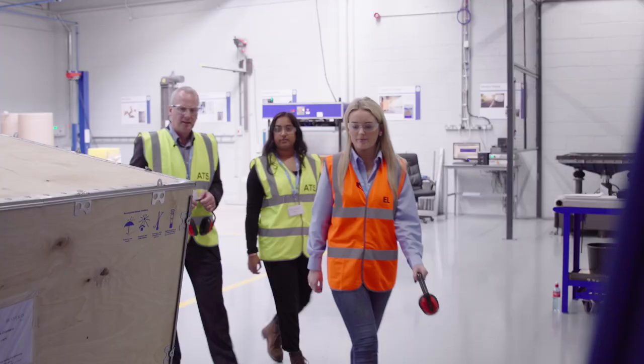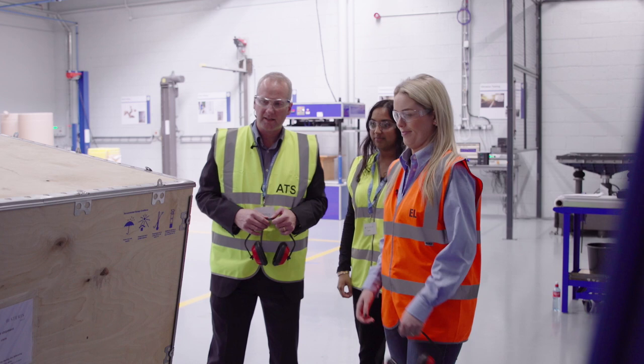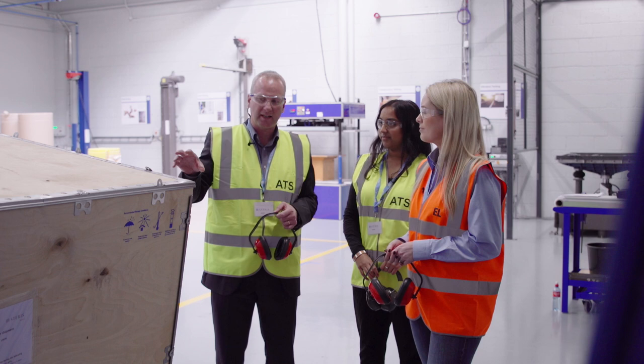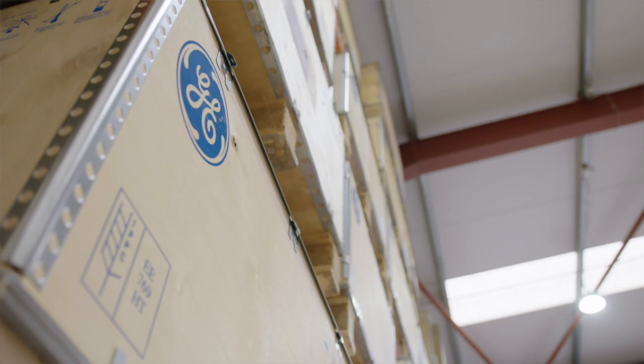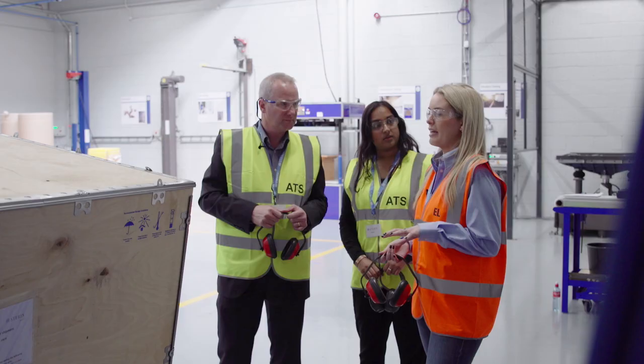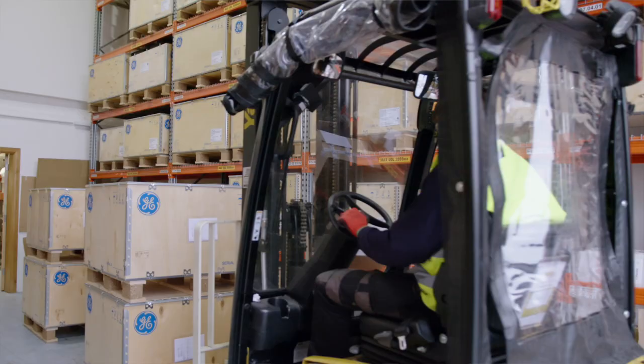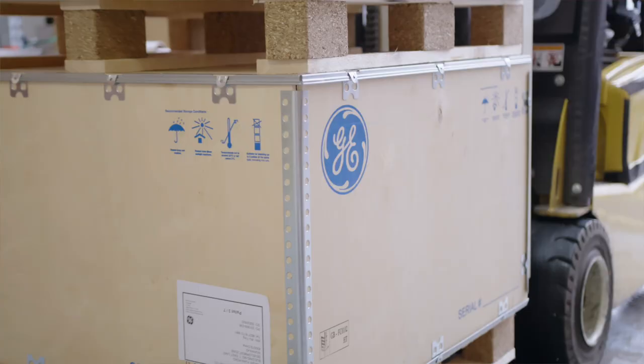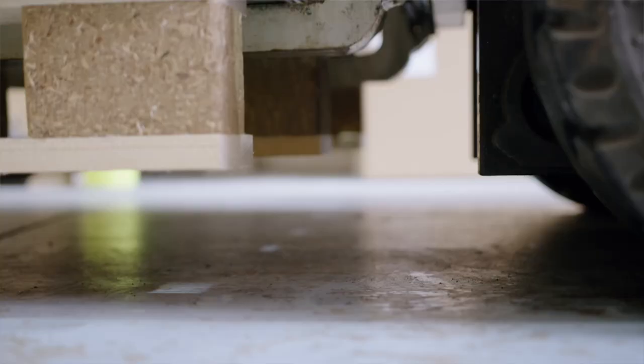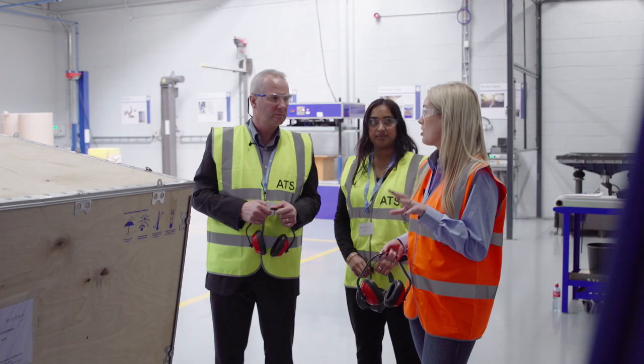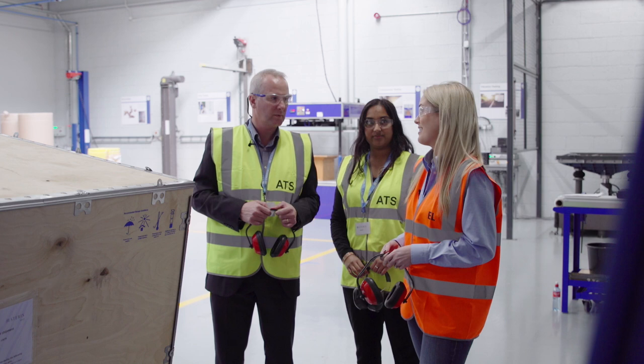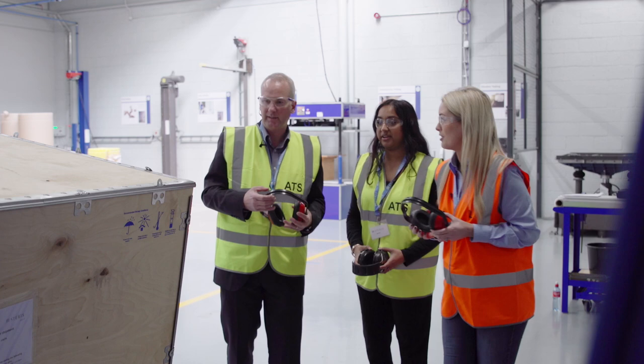So this is the pallet incline impact test. Zainab, when our products are being transported in the packaging, they also have to withstand the various thumps and bumps that they'll come across when they're being transported to their destination. So this simulates impacts and shocks commonly found within the distribution environment, for example, a forklift lifting a pallet. For GE, this is done as part of a test series under a FedEx standard. Right, okay, so the headphones. Yes, we take a step back and pop our ear protection on and have a look. Let's go.